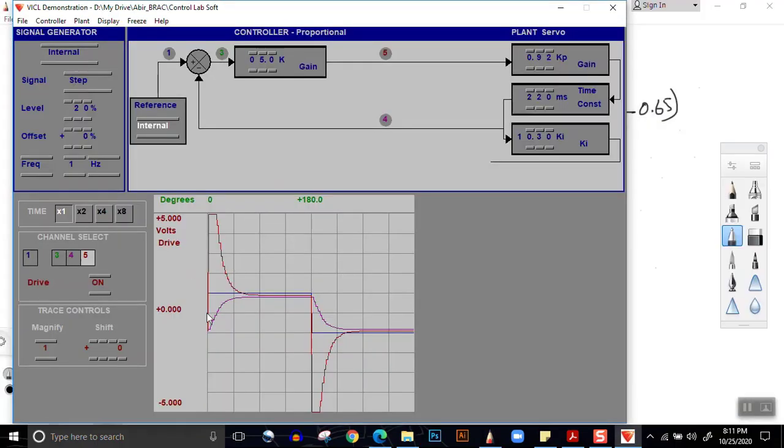For example, here you can see an abrupt change, the drive signal rises. It maintains a certain level. During that time, the output quickly increases in voltage or velocity. Then it gradually decreases the drive signal. So this is the effect of the drive signal. In observing this effect, a phenomenon comes up which is called drive saturation, which is really important. Here you see that there is a flat peak at the drive.